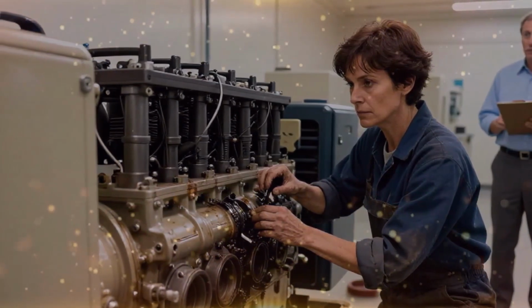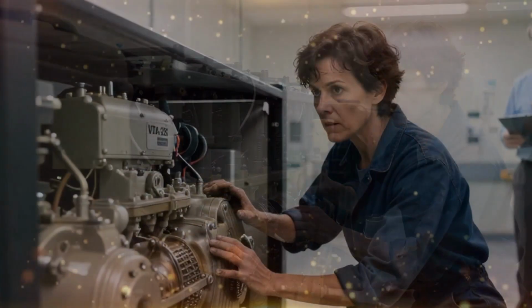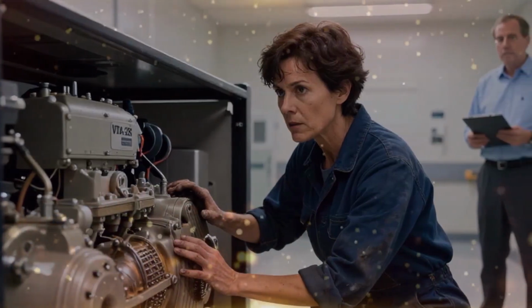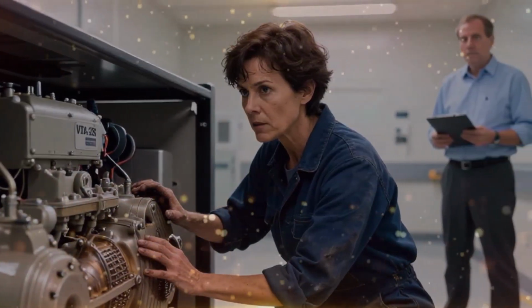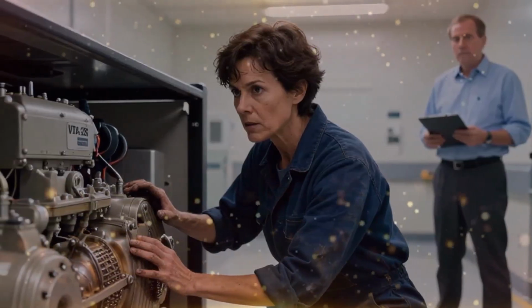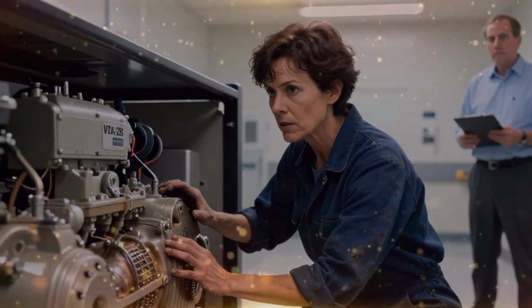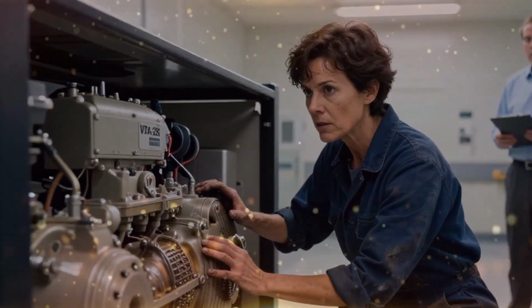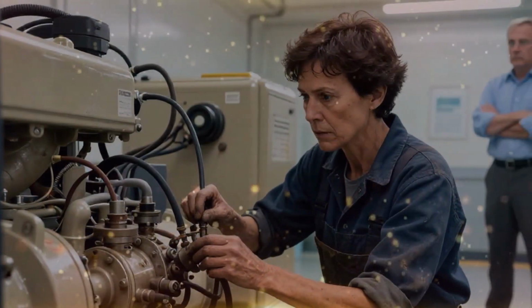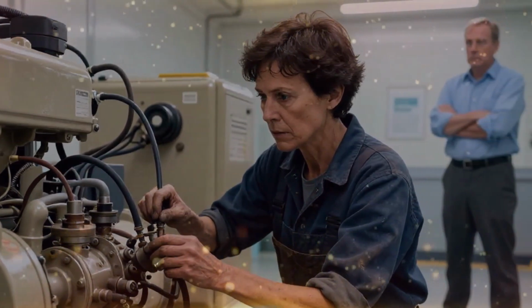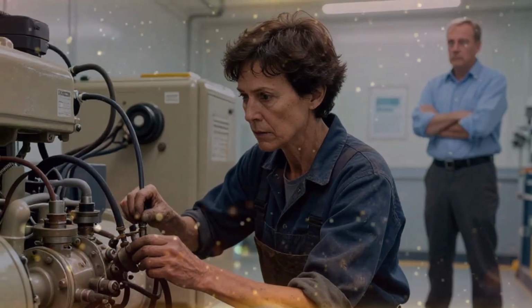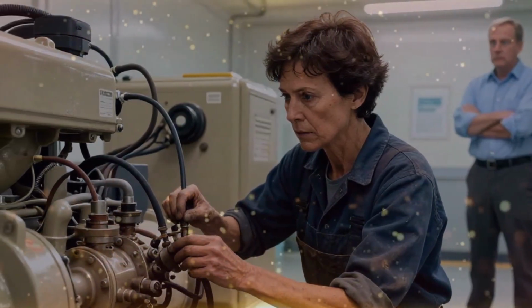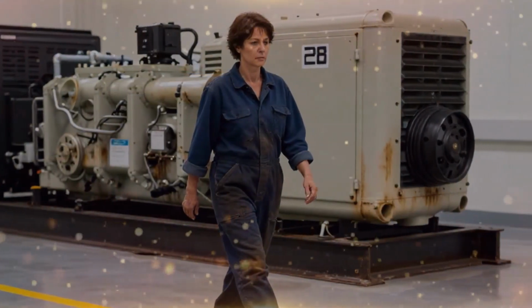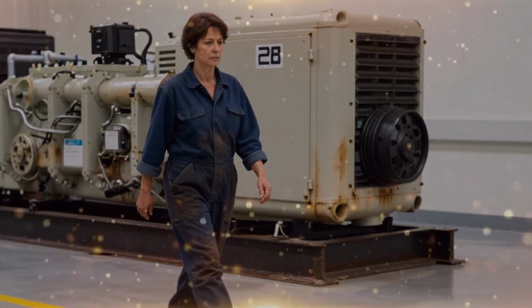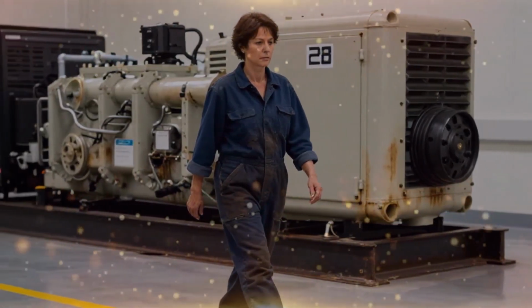To understand the scale of the failure, you have to understand the machine. The Cummins VTA28 isn't just an engine, it is a monument to a specific era of industrial might. We're talking about 12 cylinders arranged in a V formation, displacing 28 liters, weighing over 12,000 pounds. It was built in the mid-70s, a time when engineering was defined by cast iron and mechanical linkages, not silicon and software. It sits on its isolation pads like a sleeping giant, indifferent to the panic of the administrators upstairs.